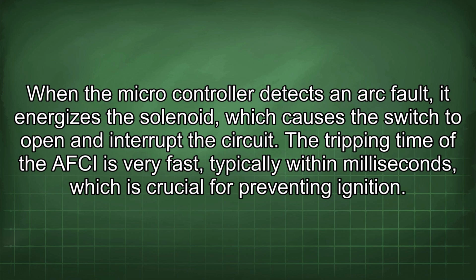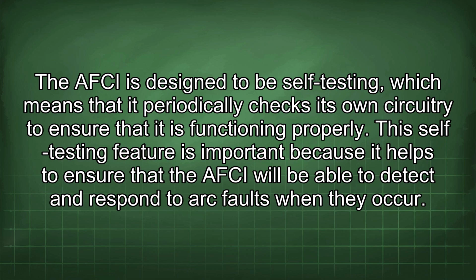The tripping time of the AFCI is very fast, typically within milliseconds, which is crucial for preventing ignition. The AFCI is designed to be self-testing, which means that it periodically checks its own circuitry to ensure that it is functioning properly. This self-testing feature is important because it helps to ensure that the AFCI will be able to detect and respond to arc faults when they occur.